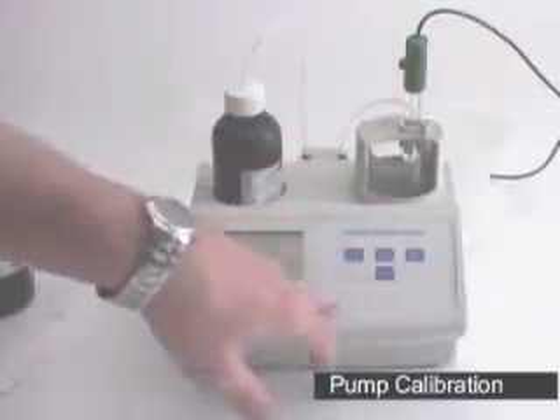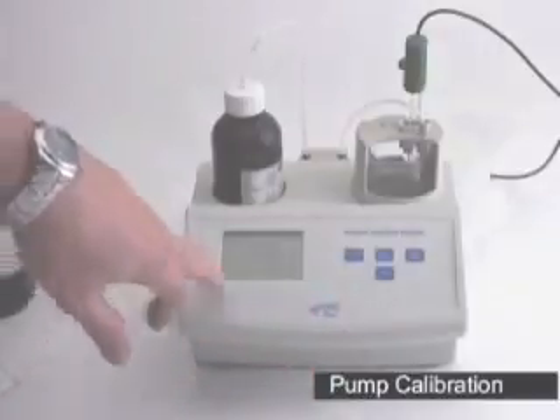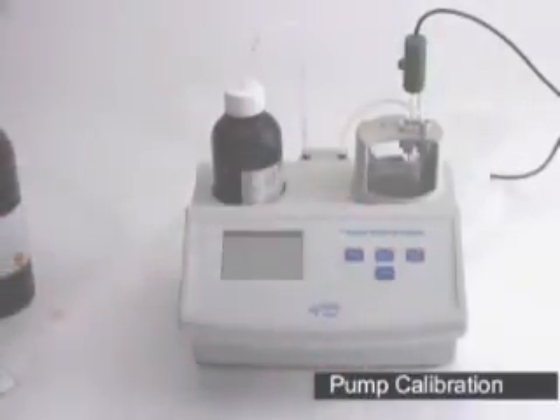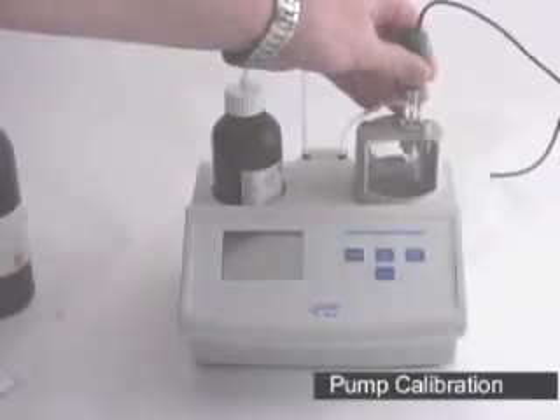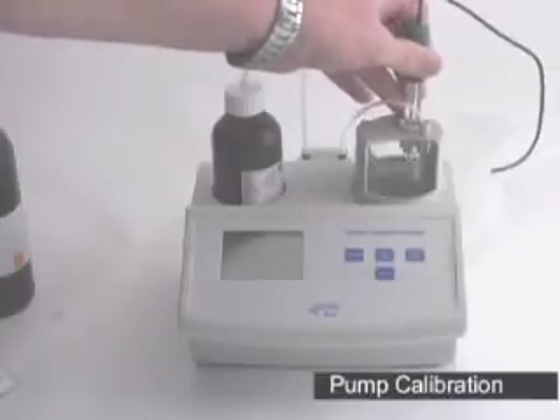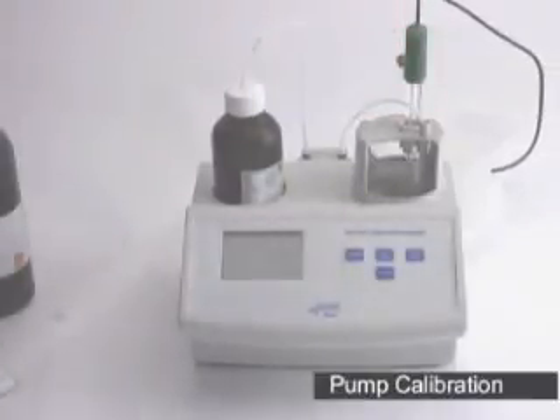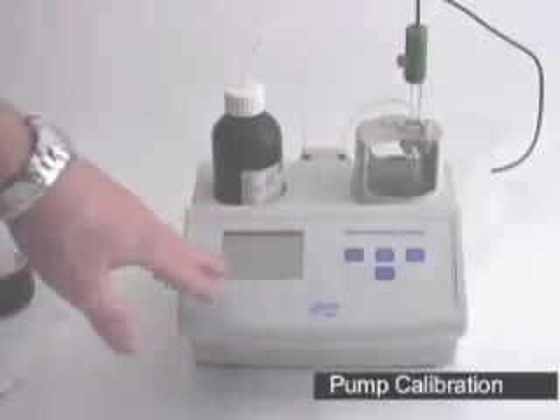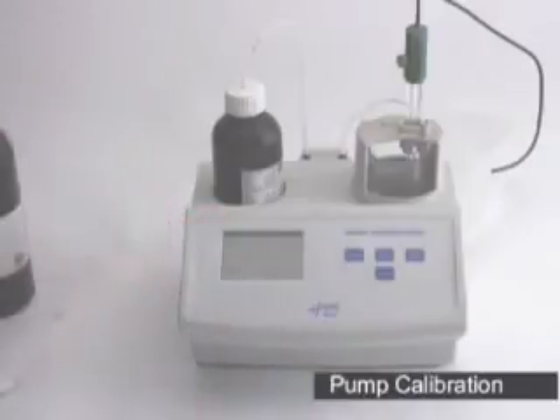Hit your cal pump button. Once standard flashes across the screen, hit start. If you hear a banging noise, just lift your probe slightly until the probe is no longer being hit by the stir bar. Once the calibration is done, we'll get done flashing across the screen and it'll go back to the 4 dashes.